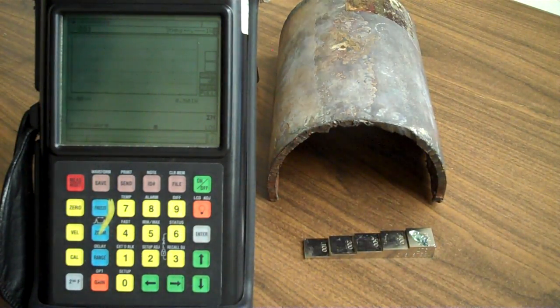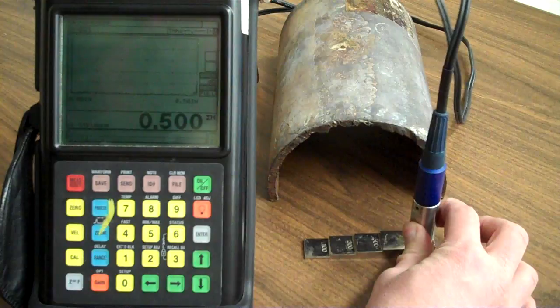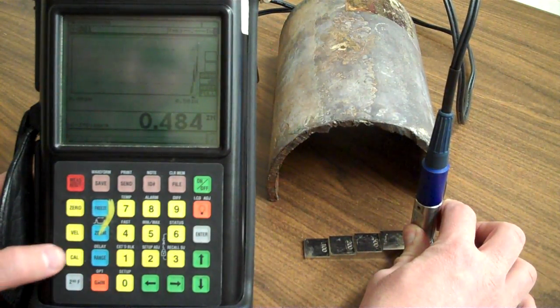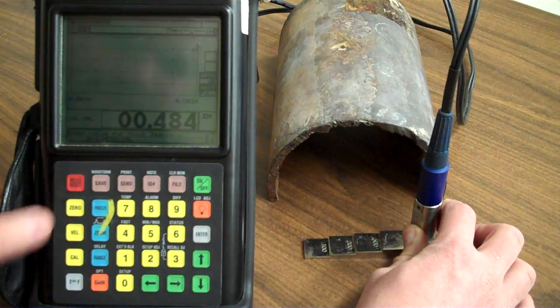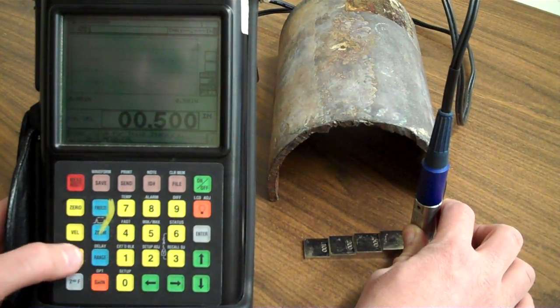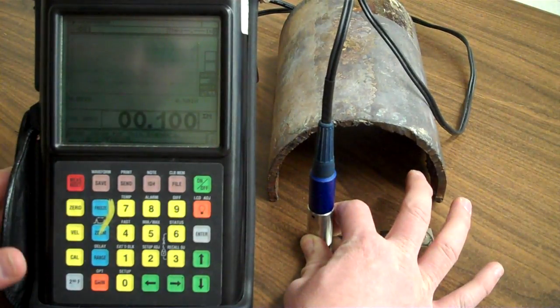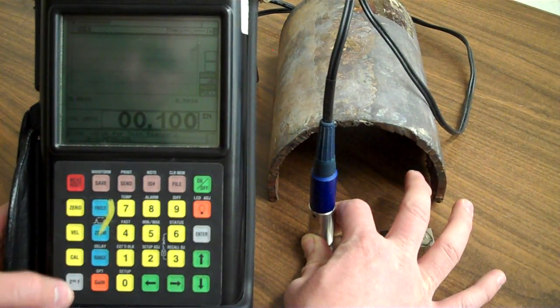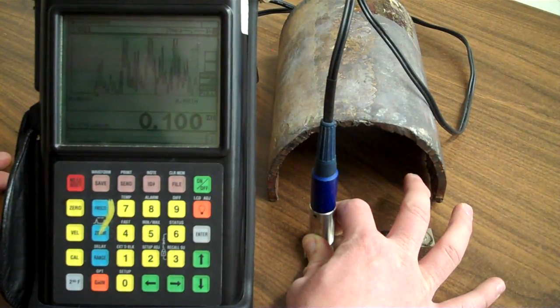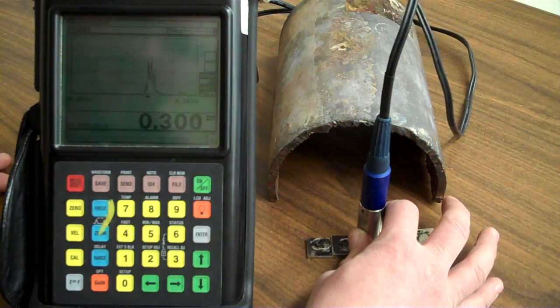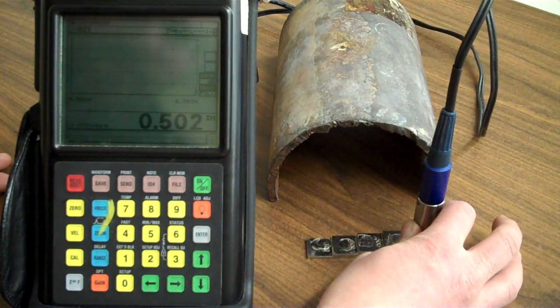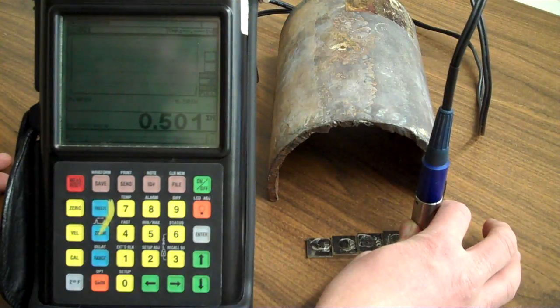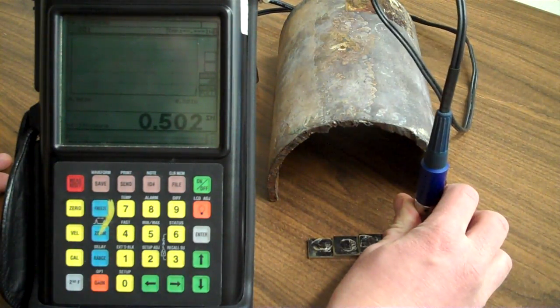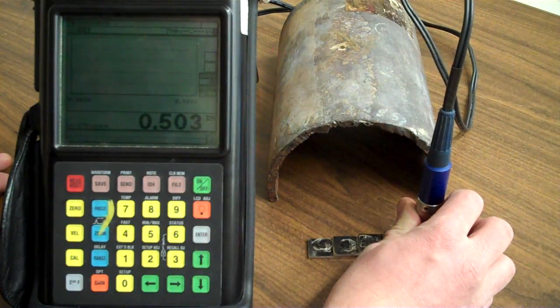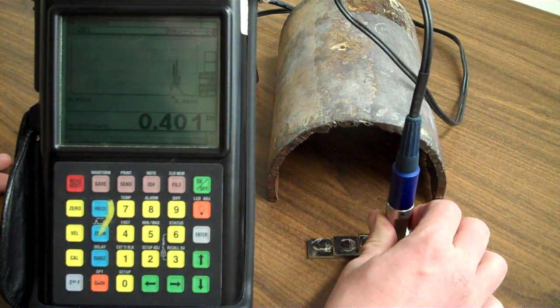Have my 5-step block here, 1/2 inch down to 1/10 of an inch. First things first, I'm just going to make that connection right there. I'm pretty close right now. I'm going to hit cal velocity. So I go thick standard. It's 1/2 inch. Cal 0. Okay, so we're good there. 1/10 of an inch, thin standard. Measure. We're within 1/1000th either way. I'd say we're probably pretty good. If I wanted to go back and get that actual 1/1000th back in there, I could go back and get the actual measurement of where it is.